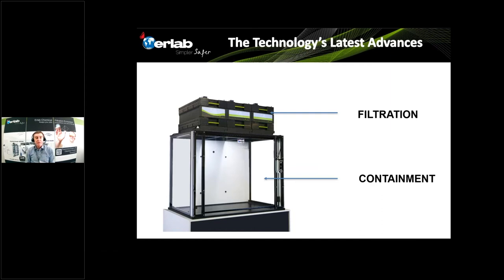The first technology is common between recirculatory filtration fume cupboards and ducted fume cupboards. It's called containment. And the other one is specific to recirculatory filtration fume cupboards: the ability to filter all the pollution emitted into the enclosure before recycling the air into the room. It's called filtration.